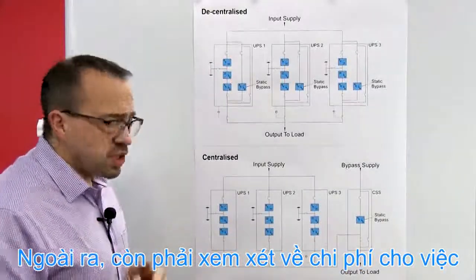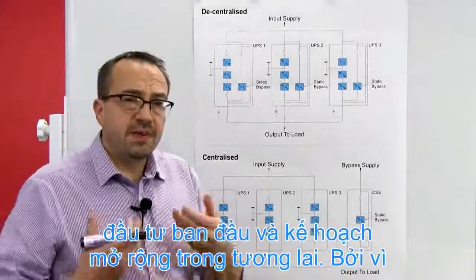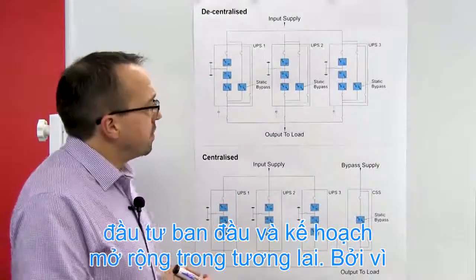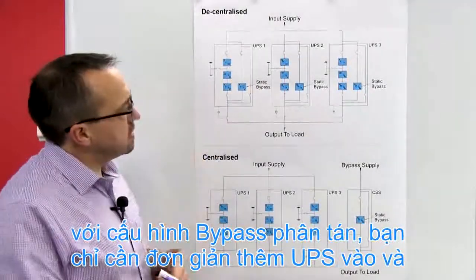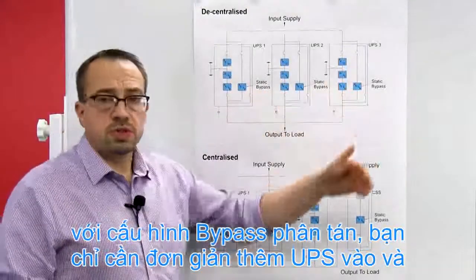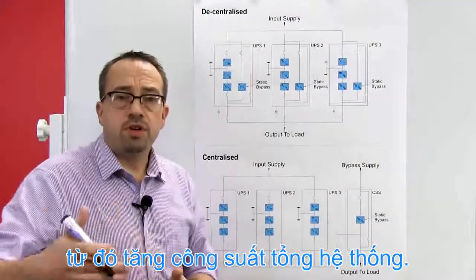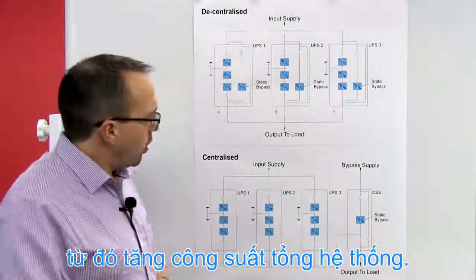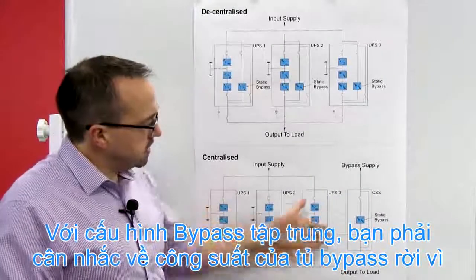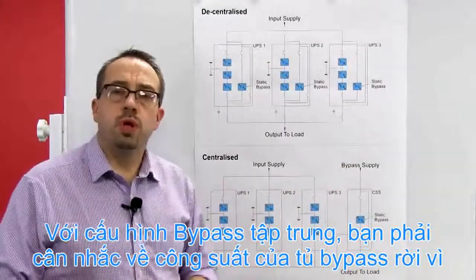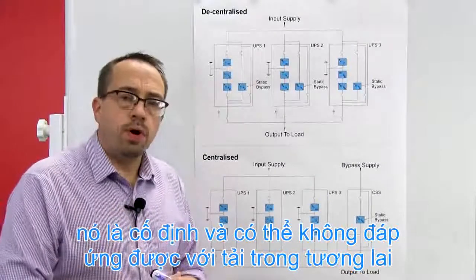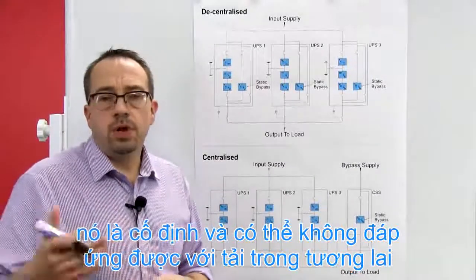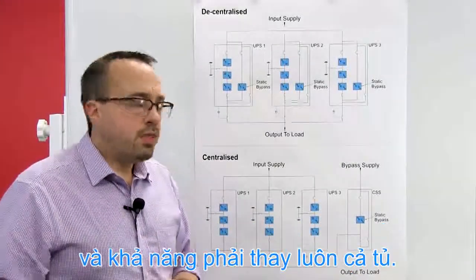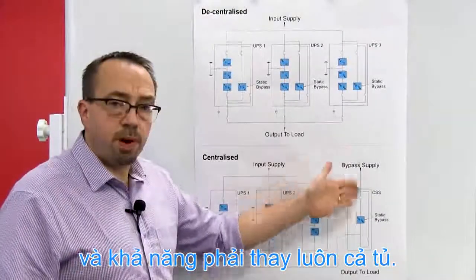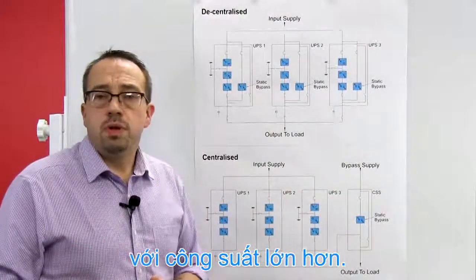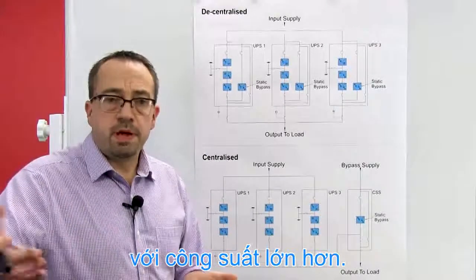In addition to the cost, you've got to consider the initial investment and the future planning, because at the end of the day, if you have a decentralized system, you can simply add modules in the future and therefore increase the capacity of the overall system. Whereas with a centralized system, you must consider the rating of the bypass module, because if the bypass module at day 1 is not rated to deal with the load that will be applied at day 2, then potentially you could end up having to replace that module with a larger module to suit the expansion in load.